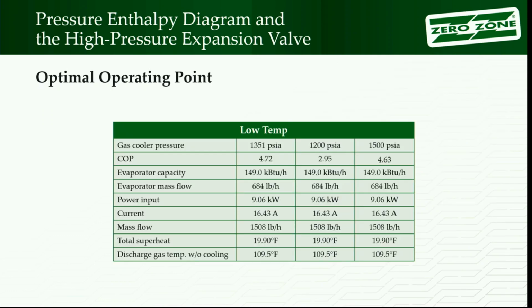So this is the table that was on the bottom of those graphs, right? Hard to read table, blew it up a little bit so you can see it. So the first column is the target, 1351. Next one over is when I thought I knew better, I was going to drop it to 1200. And then I said that wasn't working so good, so I went back up to 1500. COP, coefficient of performance for the whole system. And you can see bigger number is a better number, more efficient. So when I went to 1200 psi, I kind of took a hit.